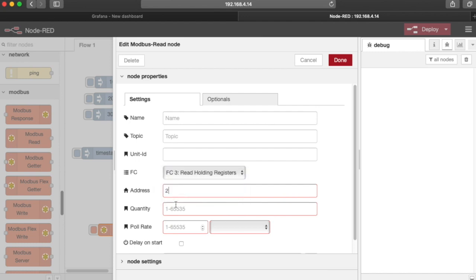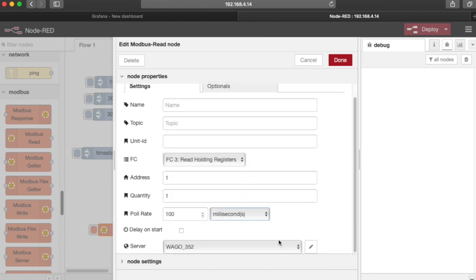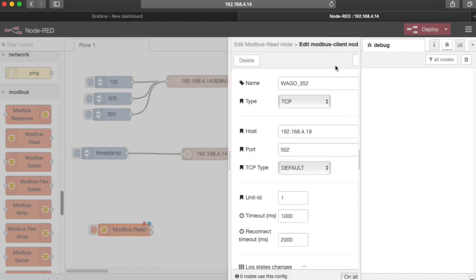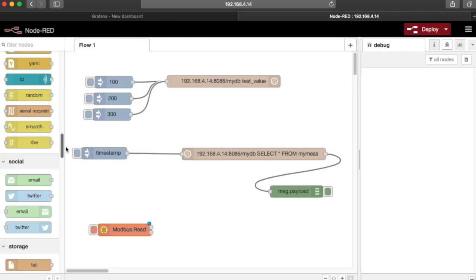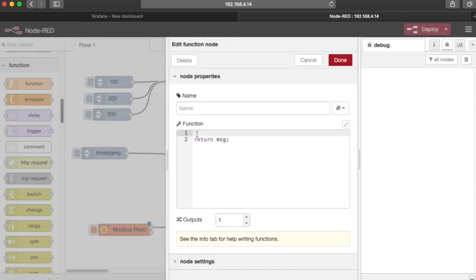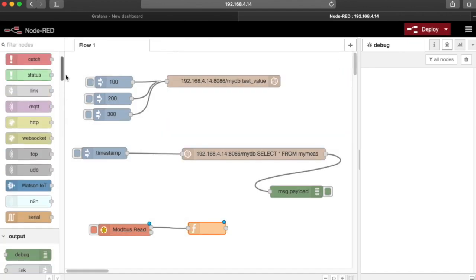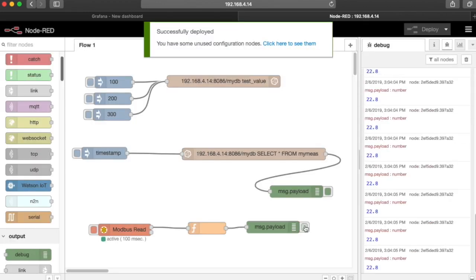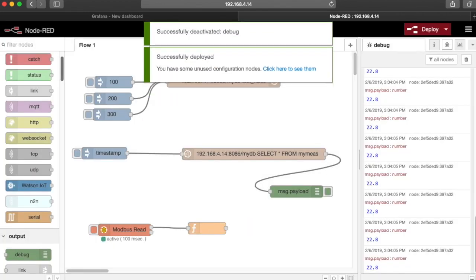Now we'll drop in a Modbus Master node. We'll use Function Code 3, and we'll read address 1. This is basically going to read the RTD that's on our coupler. That value comes in multiplied by 10, so we need to divide it by 10 in a function. If we monitor that in a debug window, you can see the values coming in.